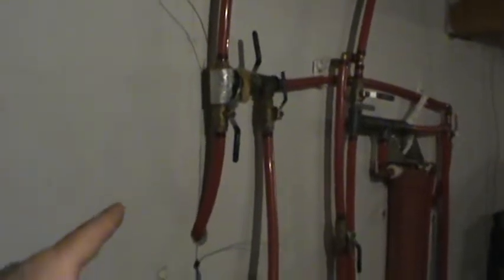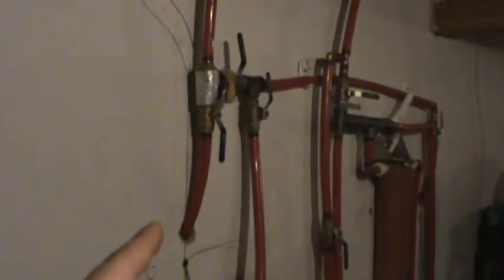I've got a bypass network set up here. The way it works is when I'm charging the tanks with thermal energy, water flows from the boiler, goes this way through this pump, and then down. So the hottest water is actually in the top of this tank on this side. There's a tank on this side, a tank on the other side. So this tank holds the hottest water. So what I want to do when there's a call for heat and the tanks are going to supply the heat to the home is have the water flow out of here and backward.